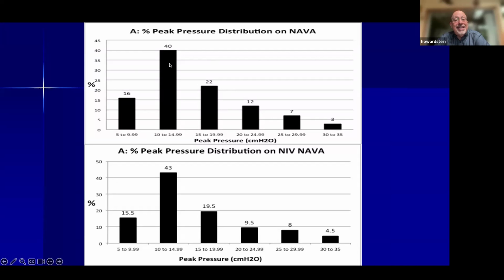If you did set your peak pressure to 15 to start with, you would fail. This baby would not do well because on conventional ventilation, they don't have the ability to recruit. But on NAVA, even though they pick the majority of their breaths to be very low pressure, they do have about 10% of their breaths at high pressures, 25 to 35. And I believe that these recruiting breaths or sigh breaths are essential to allow the babies to spend most of their time at these very low pressures.